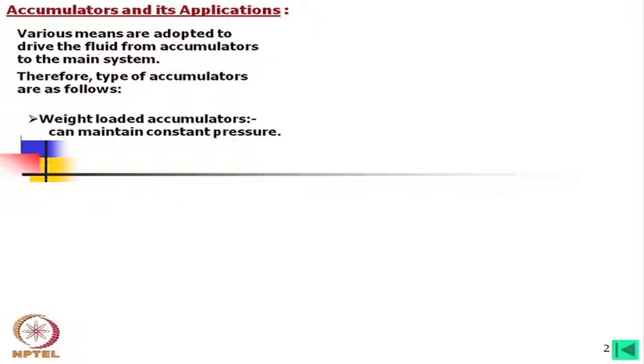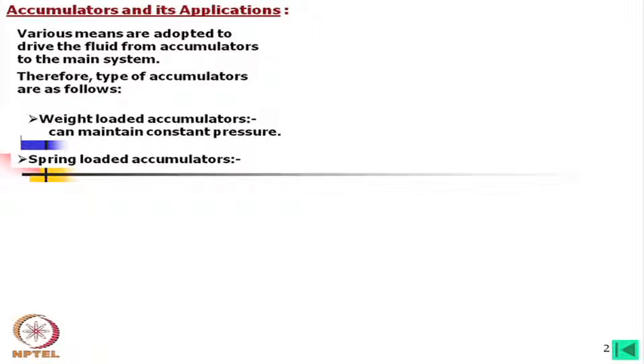Weight-loaded accumulators have the unique advantage that they can maintain constant pressure. Spring-loaded accumulators have a limitation: the force reduces when the compressive spring expands, so there will be a change in pressure — a variation of pressure.